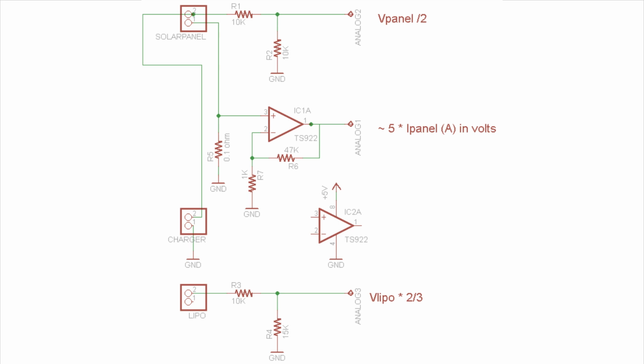But either way, your measuring circuit is referenced against what you're measuring the load of - it's part of the same circuit. The ground is the ground on both sides, whether it's high or low side sensing. There are a lot of situations where you want total isolation - no connection at all between what you're measuring and the measurement circuit.